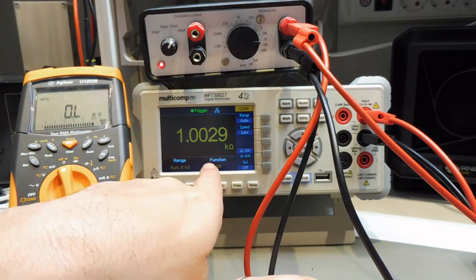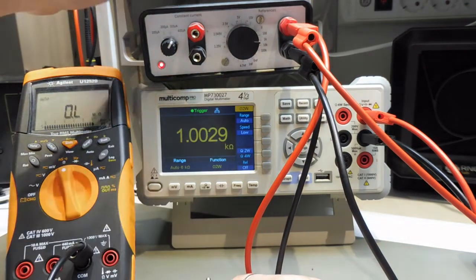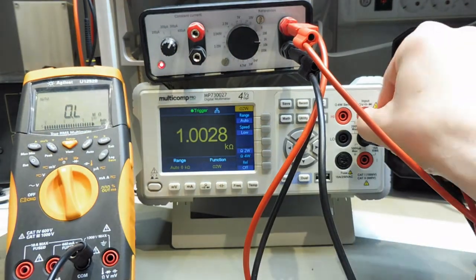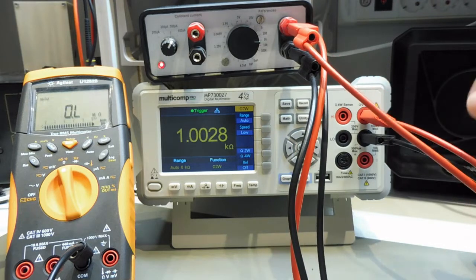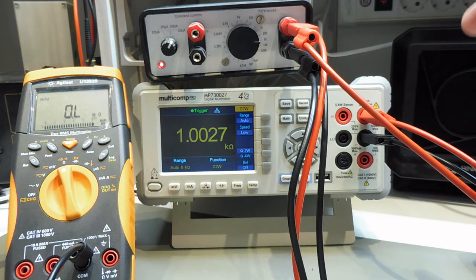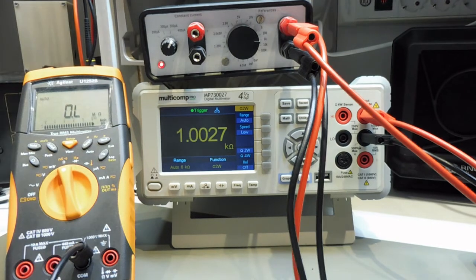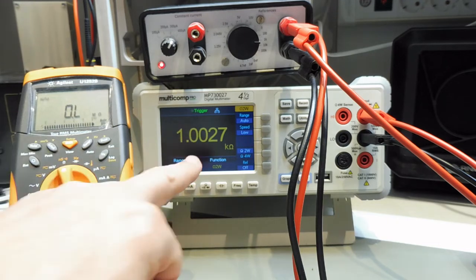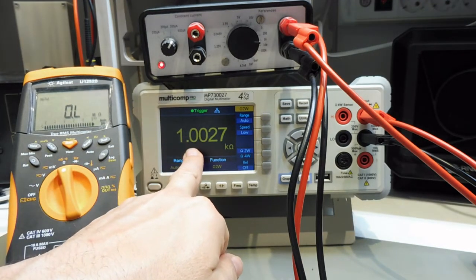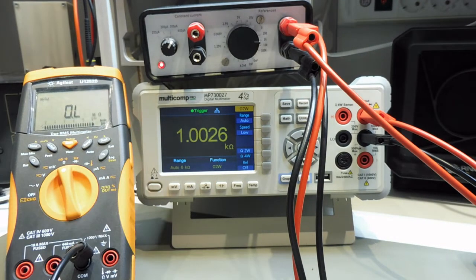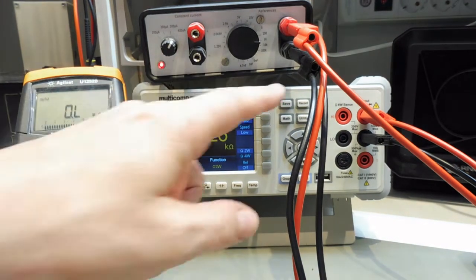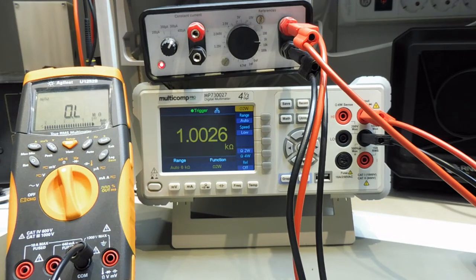Actually, it's also a 0.01% resistor here in this meter, but probably the actual leads here play a role, so probably I should use 4-wire measurement or relative measurement for this as well. But even this run here, it's 0.2%, which is probably would be out of specification, but I would need to check with the 4-wire measurement here.